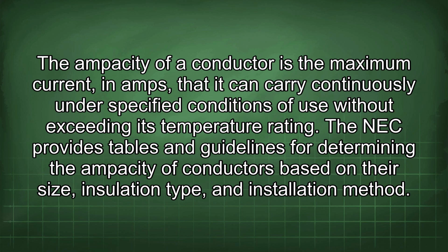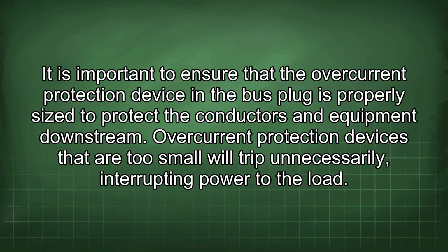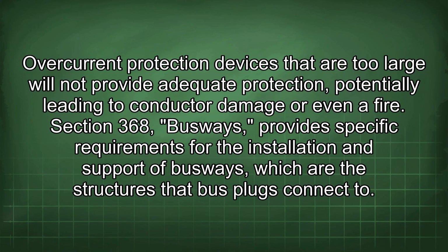The NEC provides tables and guidelines for determining the ampacity of conductors based on their size, insulation type, and installation method. It is important to ensure that the overcurrent protection device in the bus plug is properly sized to protect the conductors and equipment downstream. Overcurrent protection devices that are too small will trip unnecessarily, interrupting power to the load. Overcurrent protection devices that are too large will not provide adequate protection, potentially leading to conductor damage or even a fire.